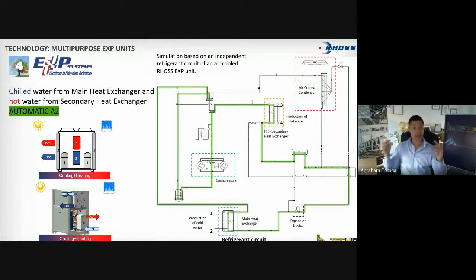So in that moment, the unit by itself senses the difference. You don't need to do anything. Say, look at, I need heating and I need cooling. So for the cooling, I'm still using the evaporator, the main heat exchanger. As for cooling, with a 1 or 2 system, a 2-pipe system there, we evaporate and we get gas in the refrigerant. We're still using the same way, going to the compressor.